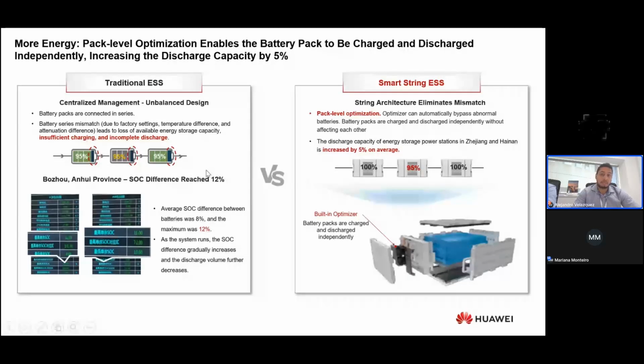This is completely avoided due to the smart string solution that we have with the 200 kilowatt hour battery. When each one has an optimizer, even if one of them is at 95%, the others are going to be giving their maximum. If there is an isolation for one, it's not going to affect the others or stop all of the battery as it would in other cases; it will just stop that particular one. And this can result in an increase of 5% on average for their lifetime.